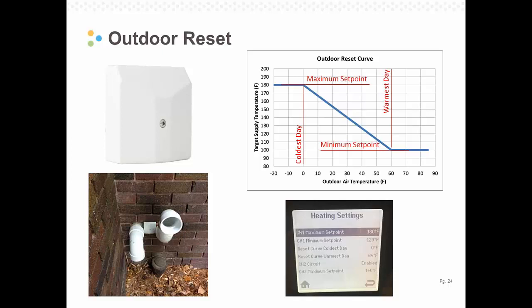So hotter water temperatures will deliver more heat to the home. On your coldest day of the year, you have the highest temperature setting. This curve shows the factory default of one boiler. The coldest day for this factory default was set at 0 degrees outdoor air temperature, and at that temperature it had a maximum supply water temperature of 180 degrees.